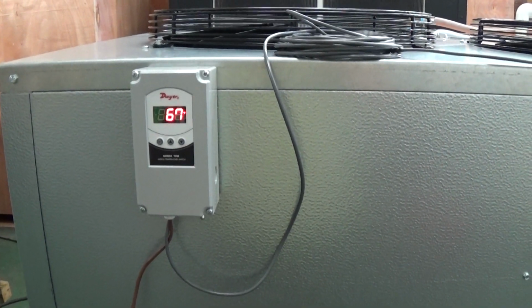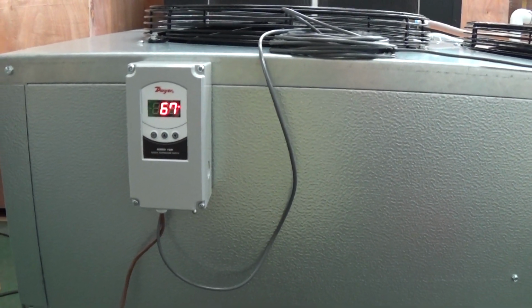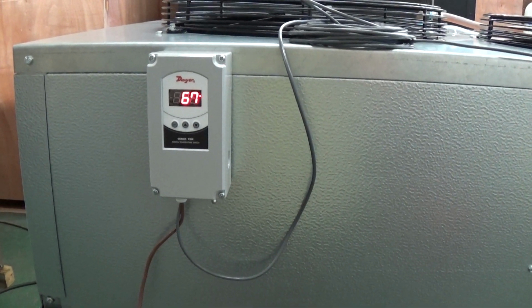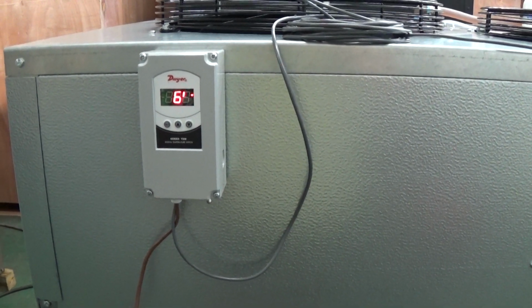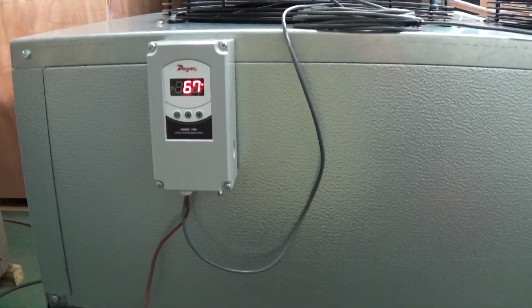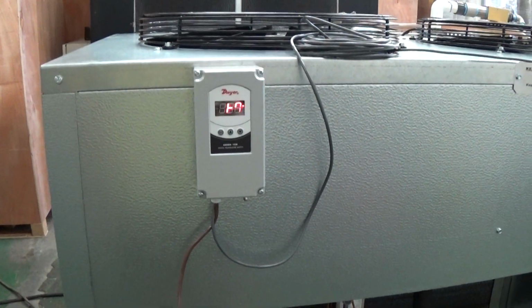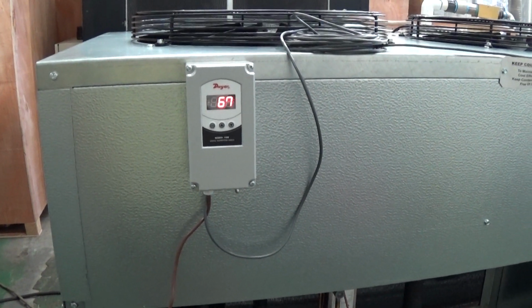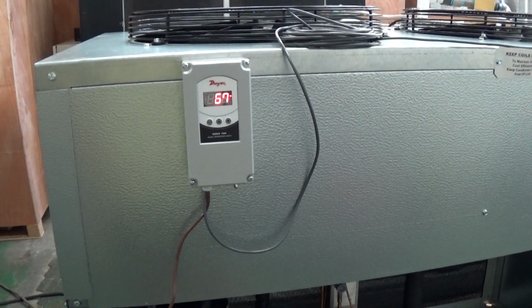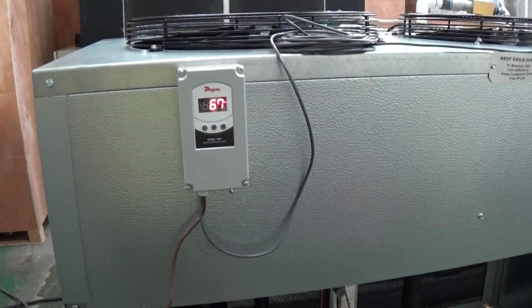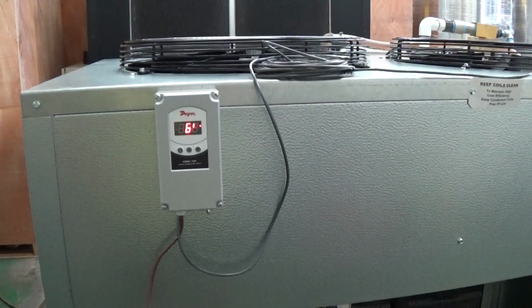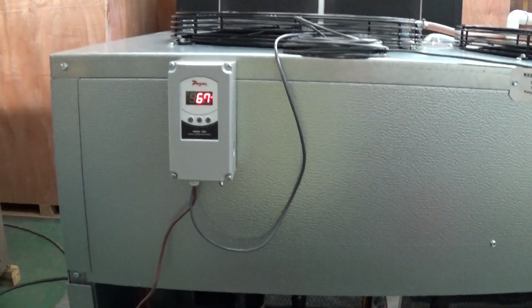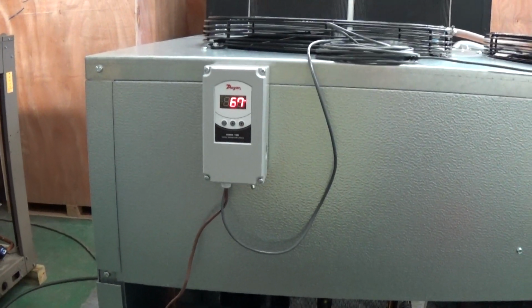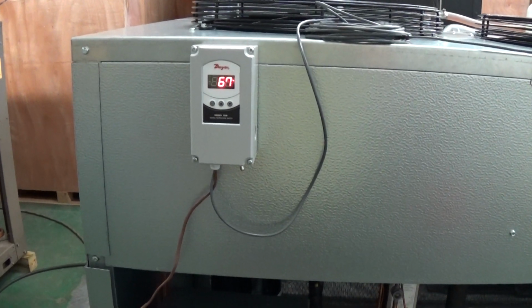If it's a unit running standard temperatures, when it leaves the factory, you'll have a minimum set point of 44 degrees Fahrenheit. If it's a glycol chiller, the controls will allow us to go down to approximately 25. In this case, for our testing, we have it configured to go as low as 25 Fahrenheit. When you do that, you want to run 40% glycol concentration, or even up to 50. No more than 50, that's too strong.